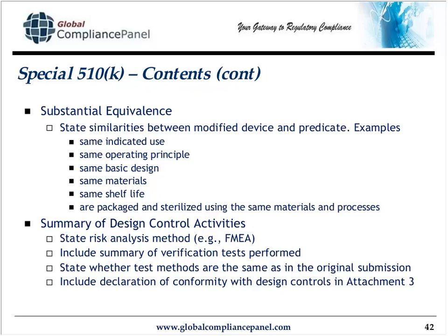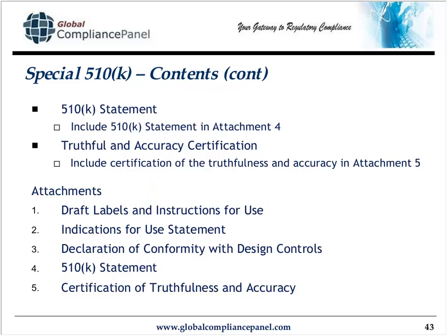And then a declaration of conformity with design controls is attachment 3. I'm going to have my 510K statement as attachment 4. My truthful and accuracy certification as attachment 5. This is a quick summary for you of the attachments in a special 510K.